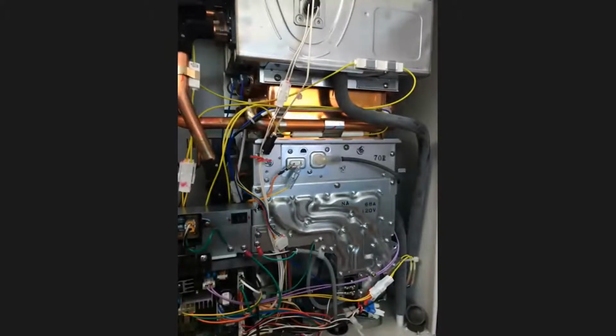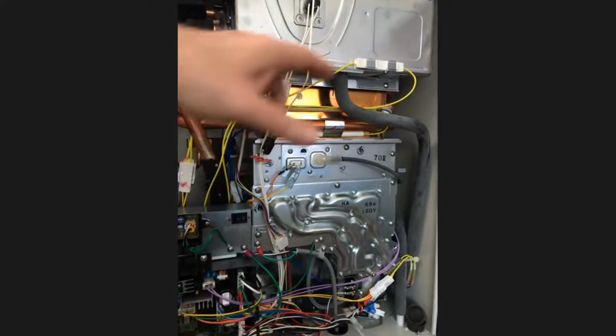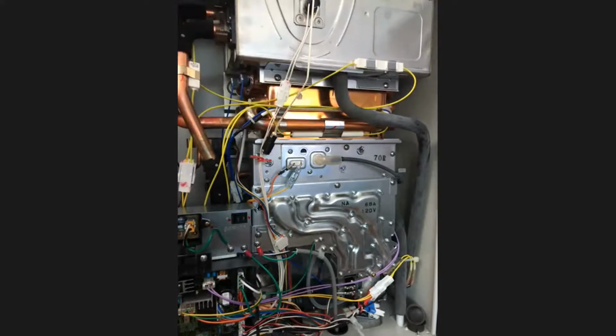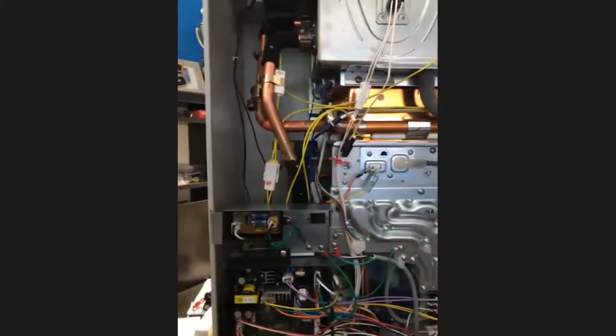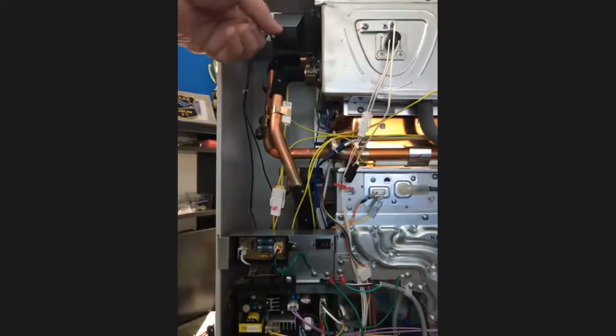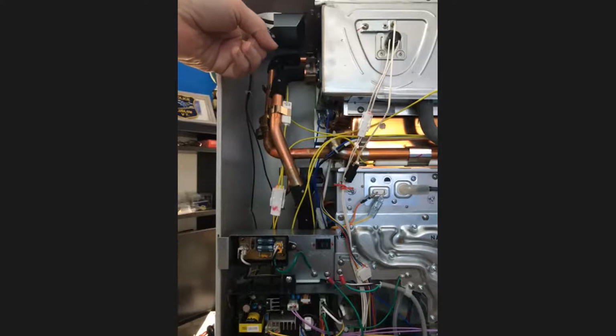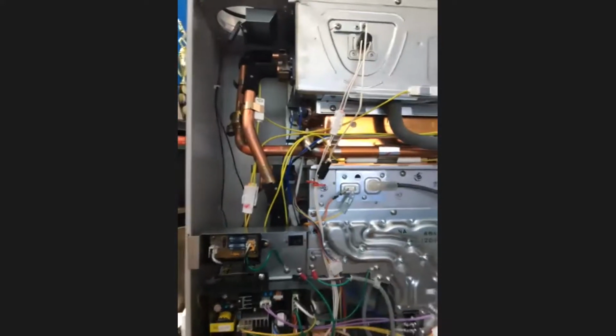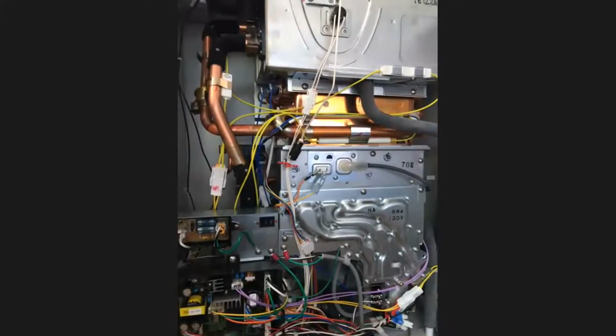As we look around, you see a lot of these yellow wires, these little resistors. This is actually my freeze protection. I've got a sensor mounted right up here at the top - this is my freeze sensor. If I'm sensing that, I can actually heat the pipes within the unit and do some freeze protection. So that's what we have there - a little freeze protection built in.